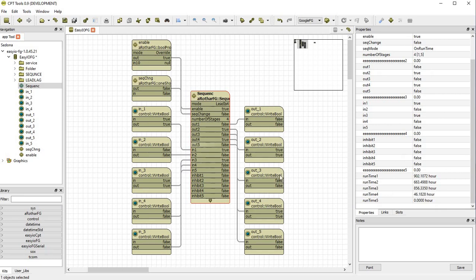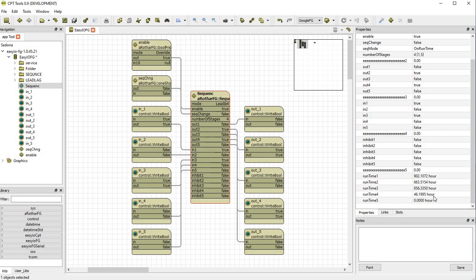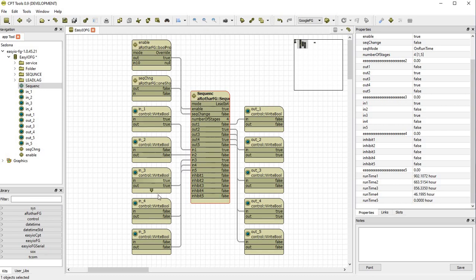So if we turn one off and turn one on again, two will turn off and then two would turn back on again. And if we ran a sequence change now, there would be no change of outputs because we're running on runtime. So four will remain as the lead unit until it catches up the 620 hours to get to runtime two. And the same, two will remain the second unit until it hits over three.